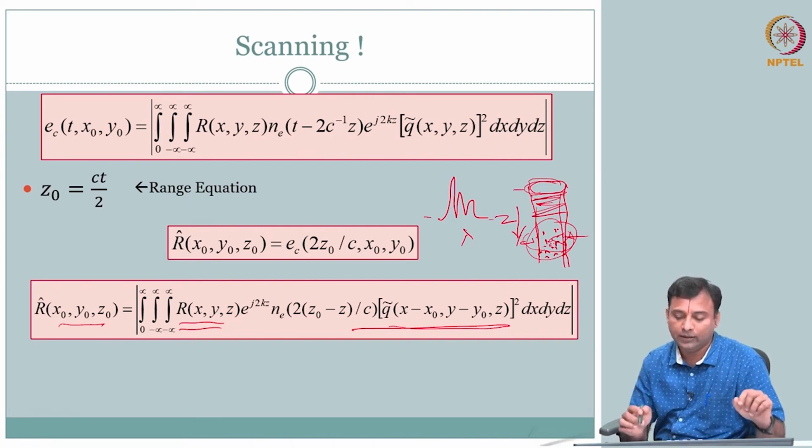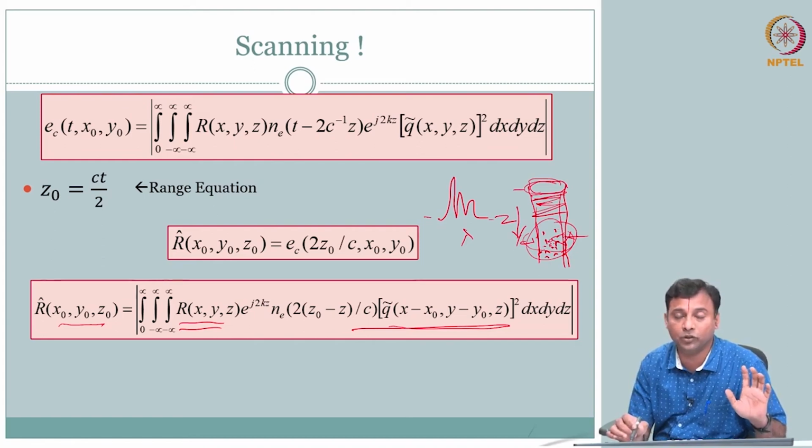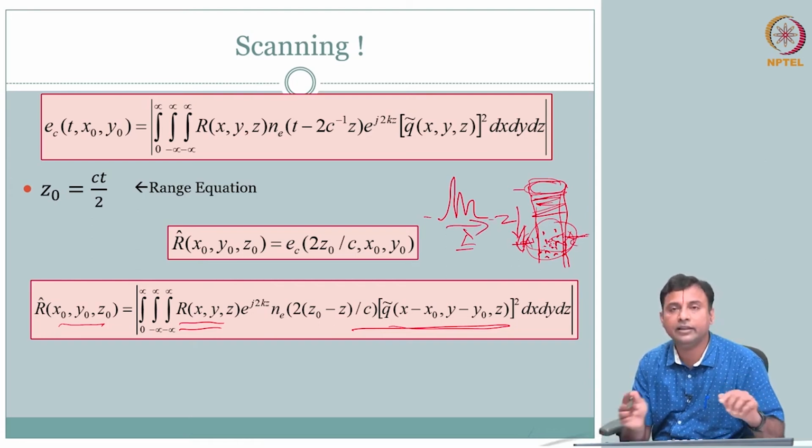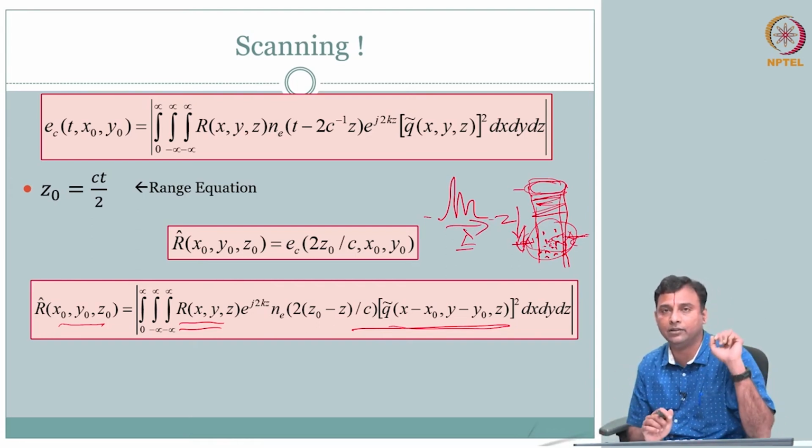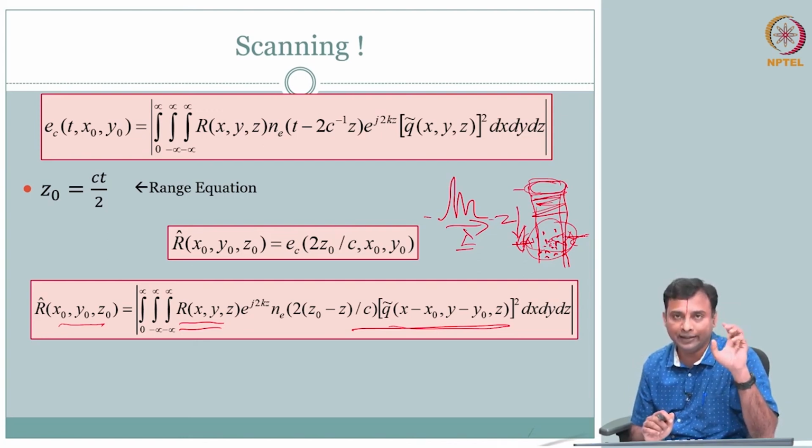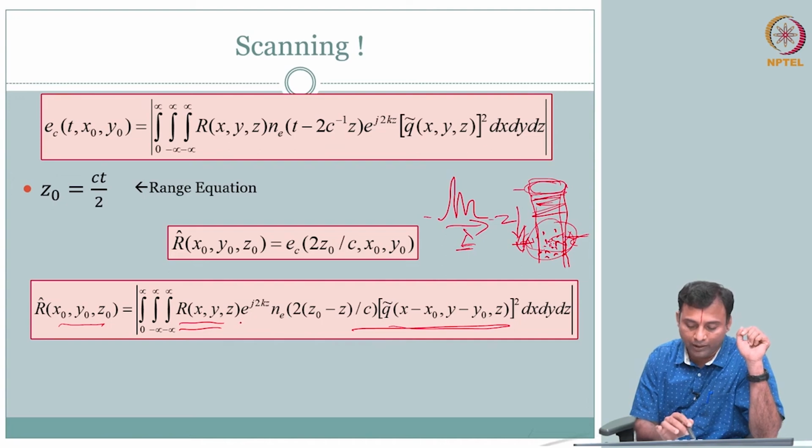However, you notice that that is one important aspect. The resolution cell, which is in terms of lambda, has an effect on resolution. So how much can you make it in the axial direction, and the beam width in the lateral and elevational directions. All this dictates your resolution, and it is not the same. In ultrasound it is not the same. In the axial direction you have better resolution than your lateral width and elevational width. And then you notice one another term here.